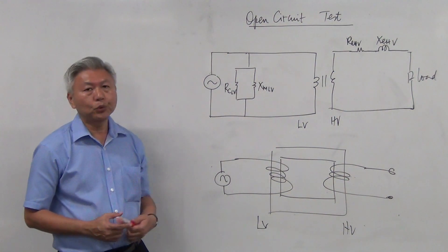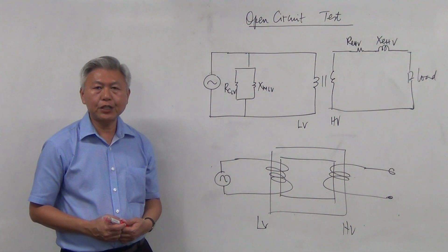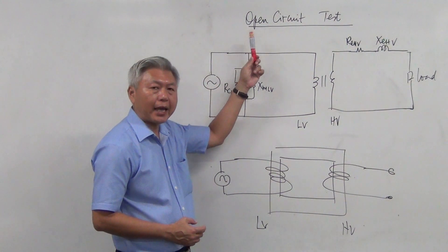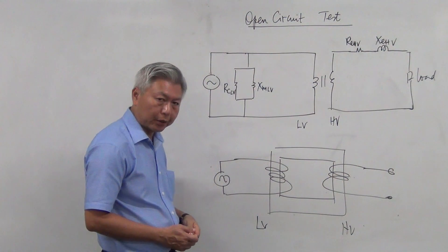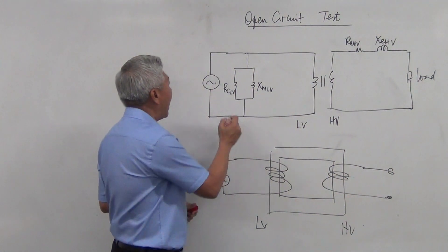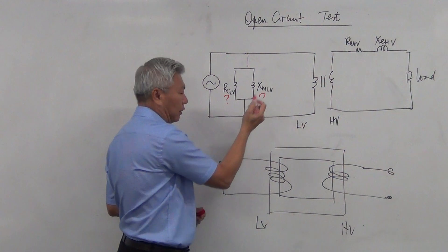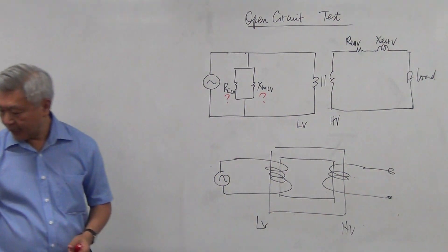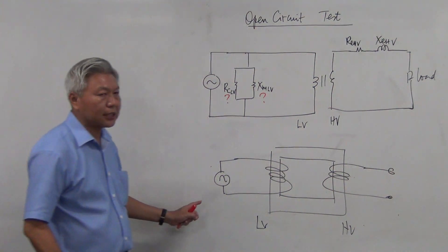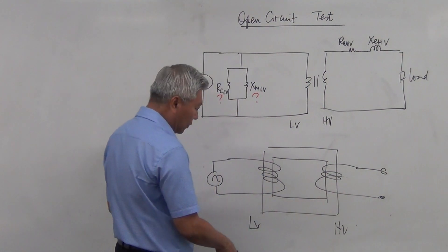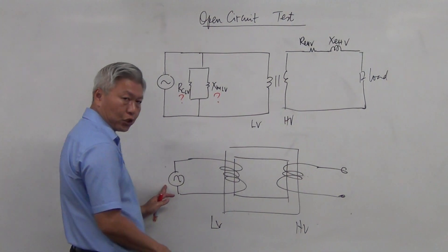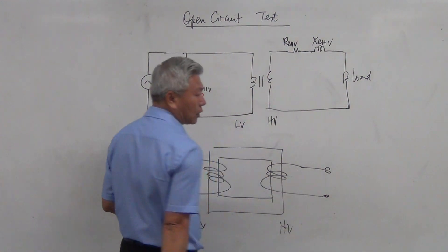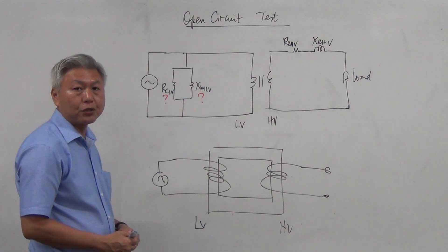Now let's come to this transformer — a very interesting experiment called the open circuit test. The purpose of this experiment is to get the values of RC and XM. What is entailed is that you have a transformer, you apply voltage at the low voltage side, and you leave the high voltage side open circuit. That's why it's called the open circuit test.